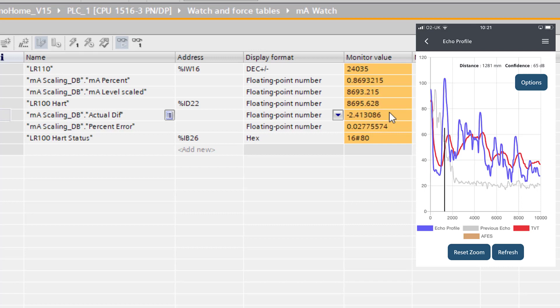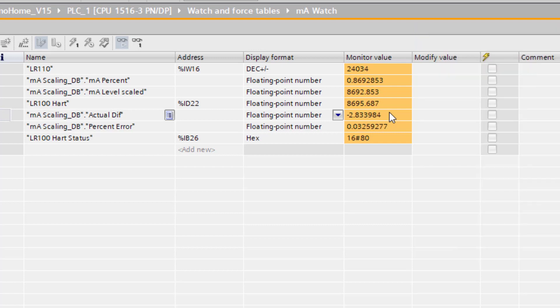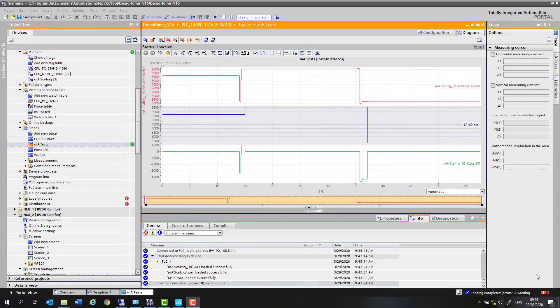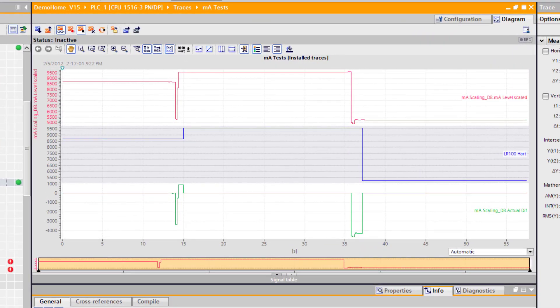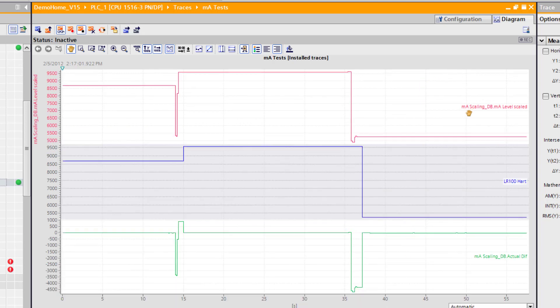We do have the problem with response time, which is what we're going to look at next — to see really, is it that bad? In my opinion I don't think it is. We'll have a look and log that with the logger feature on TIA portal. I have my trend set up — my radar is looking at a target about four and a half meters away — and I'm going to start that recording. The top trend in red is my milliamp value, I have my HART value, and I've put the difference between the two at the bottom as well.